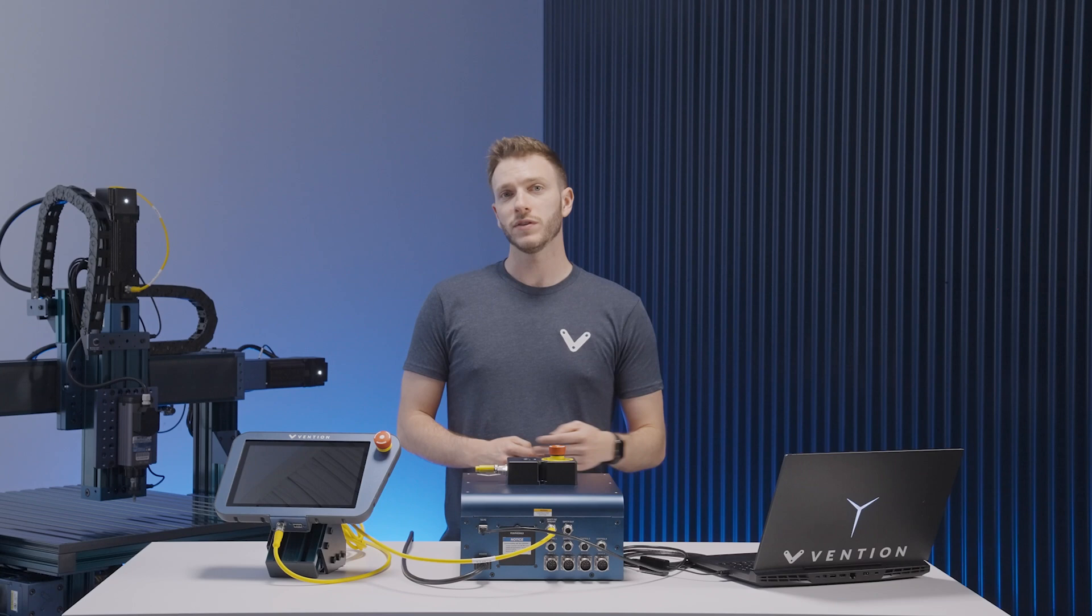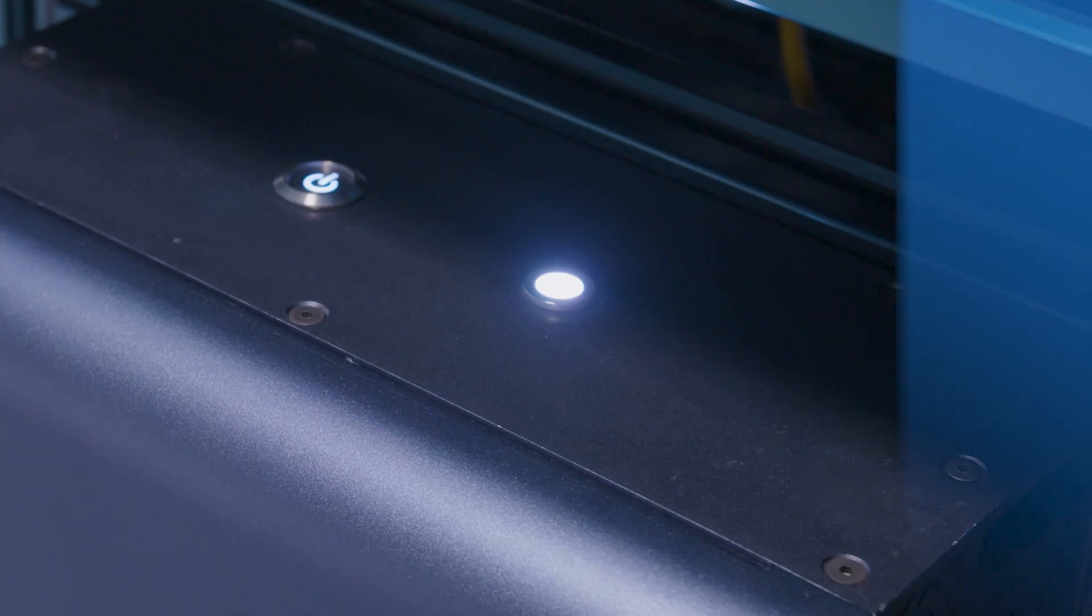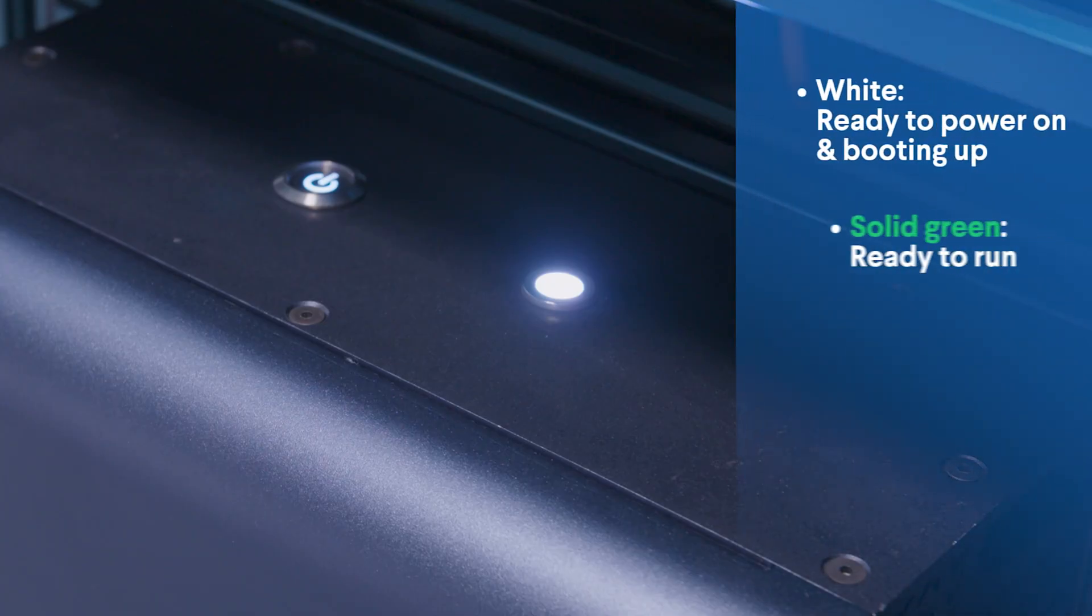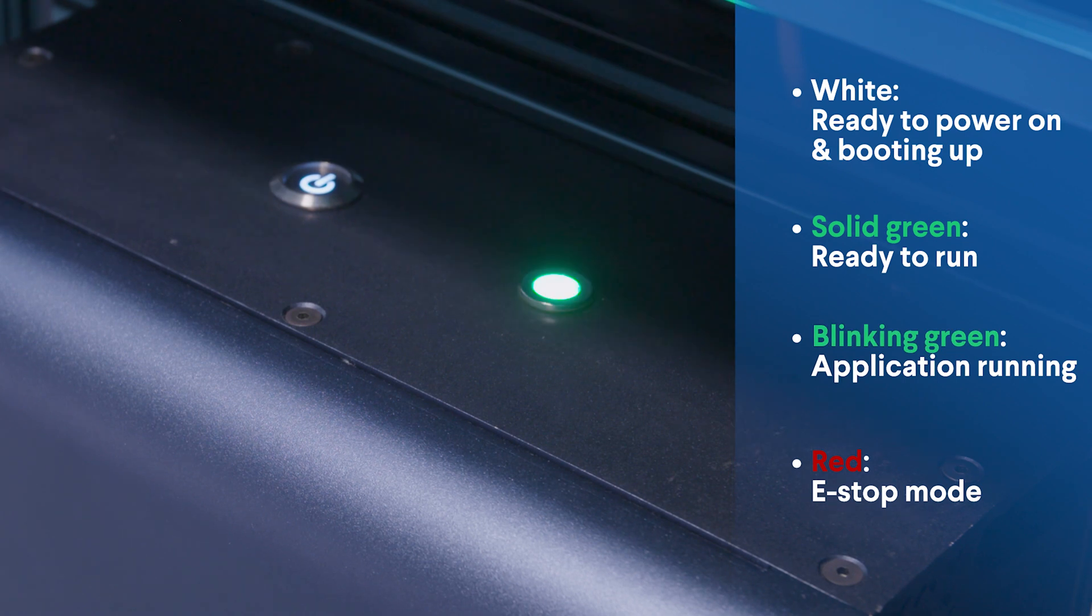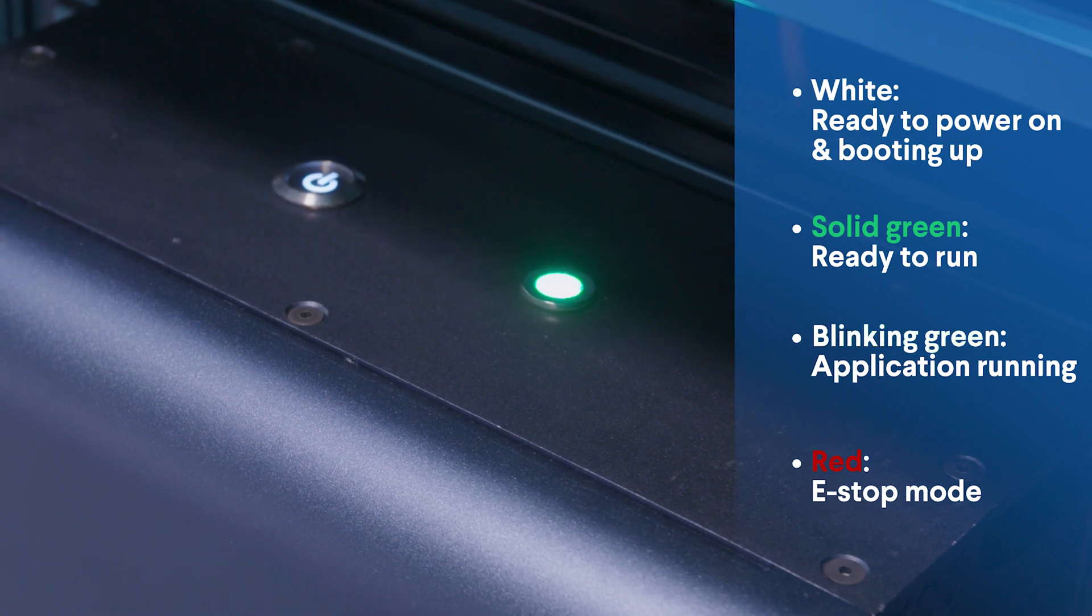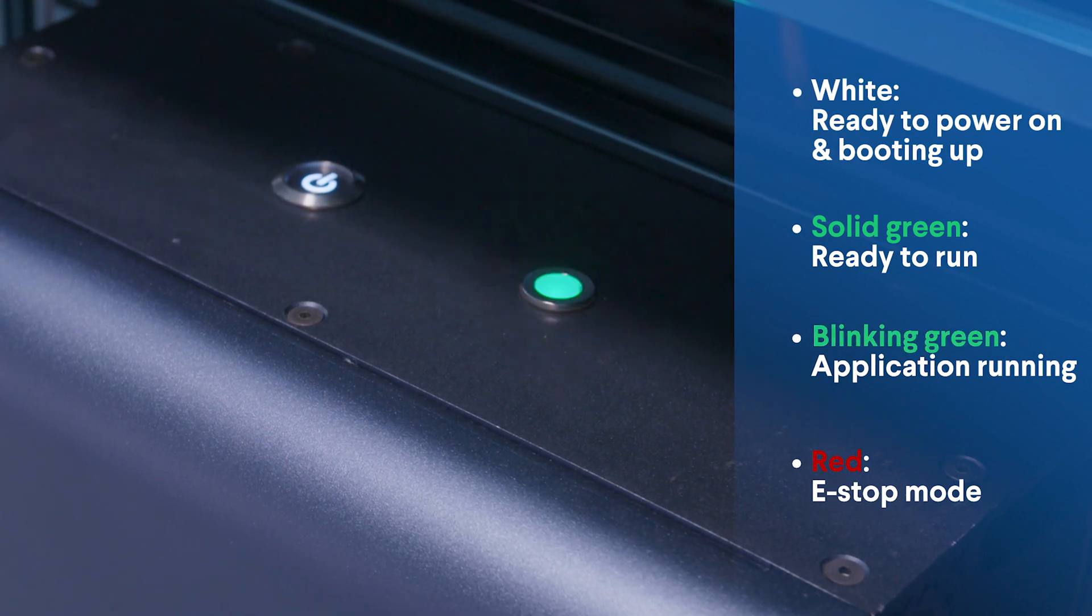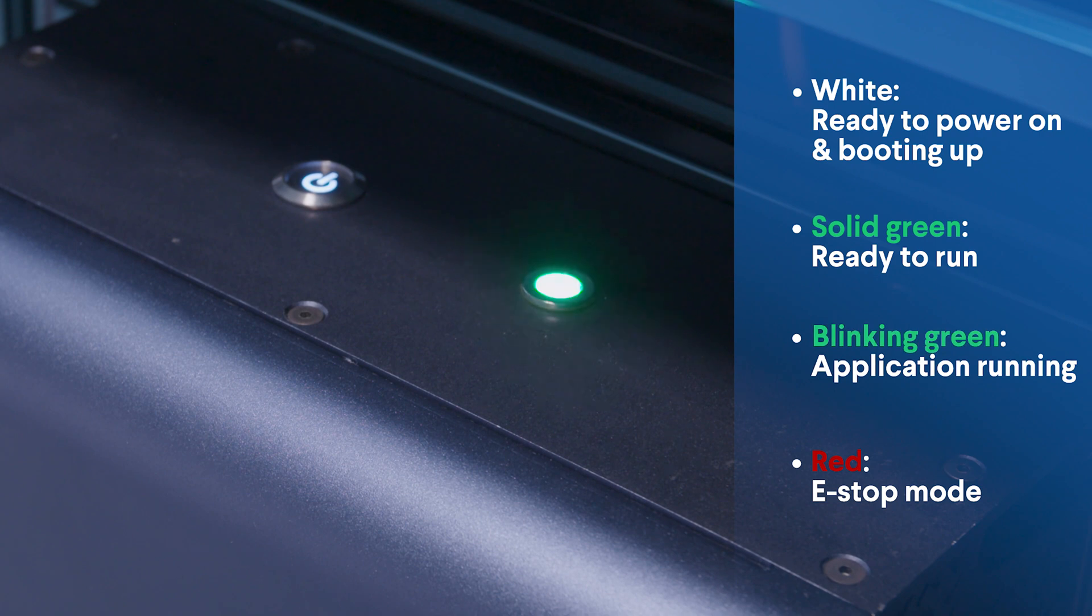There are four different states for the LED. White indicates that the controller is ready to turn on or is in the process of booting up. Solid green indicates that the system is booted and ready to run. Blinking green indicates that an application is currently running and red indicates that the system is in e-stop mode.